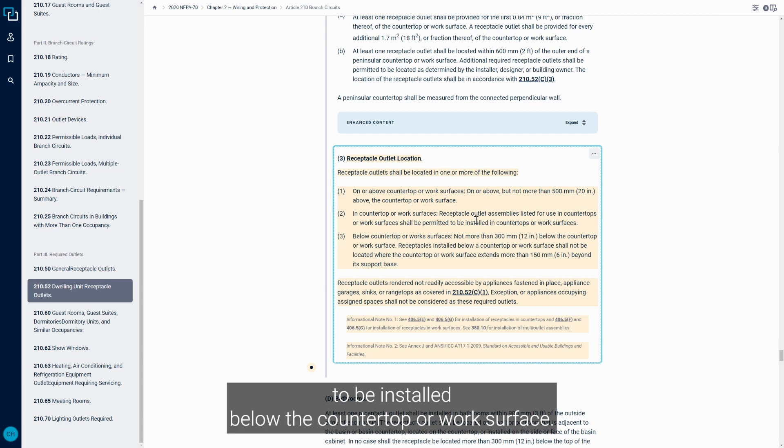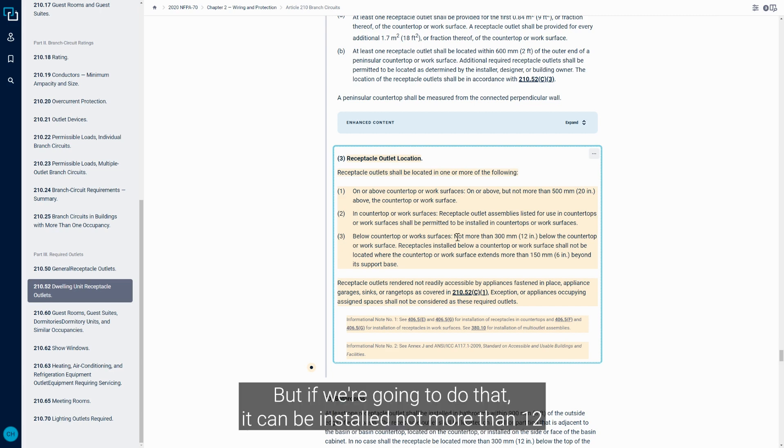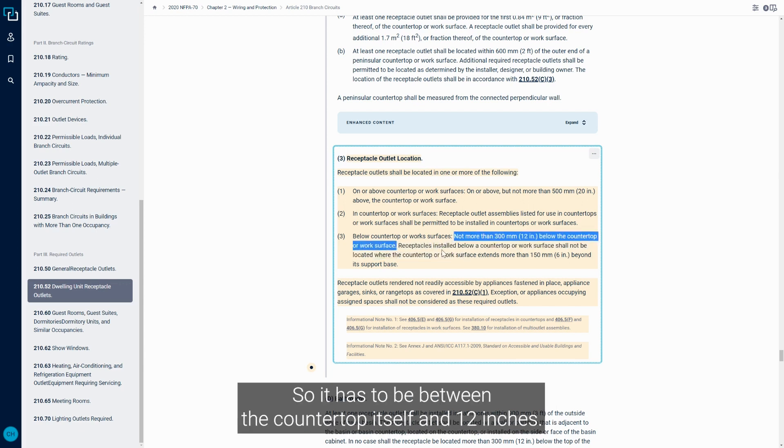Part three permits the receptacle to be installed below the countertop or work surface, but if we're going to do that, it can be installed not more than 12 inches below the countertop or work surface. So it has to be between the countertop itself and 12 inches - it cannot be installed below that.